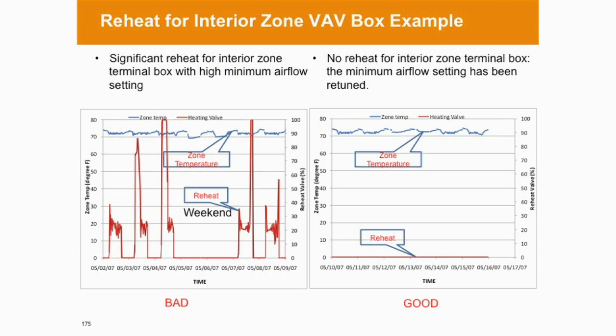So this is one more example. On the left-hand side, you can see the heating valve position for this terminal box. The zone temperature is the blue line. The red line is the reheat valve. They have the unoccupied reset schedule, but you can also see there's significant reheat for this box. This is serving an interior zone. Do you think we need that much heating for an interior zone box? Some, maybe, but a lot of the time you probably don't need it.